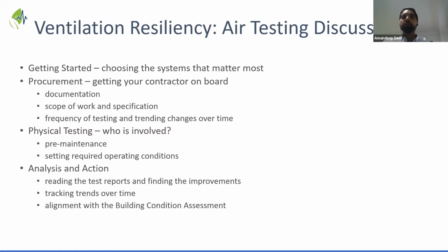And then also focus on resolving any existing pressurization issues within a department or across multiple floors that you've noticed over the years and haven't been resolved. Addressing those systems as a first priority is going to give you buy-in from the IPAC as well as the facility side. You will have better comfort. Once you improve the comfort and meet the code requirements, the energy efficiency comes along with it. As soon as you fix those systems, you're definitely going to save energy, and then you can focus on energy efficiency and making sure the systems are working as intended.